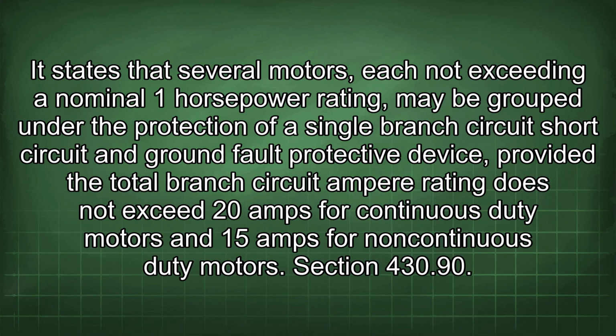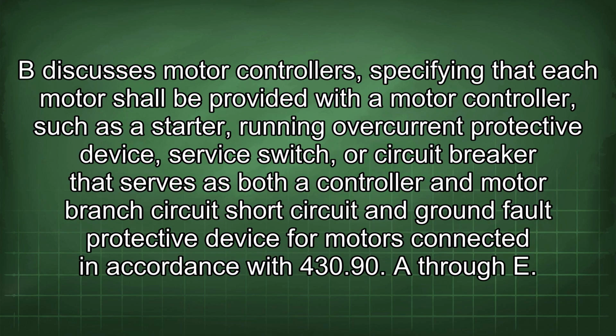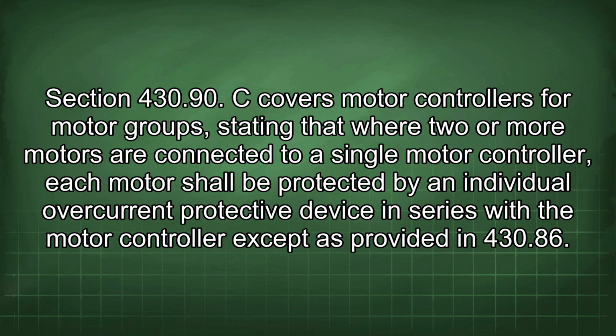Section 430.90 B discusses motor controllers, specifying that each motor shall be provided with a motor controller such as a starter, running overcurrent protective device, service switch, or circuit breaker that serves as both a controller and motor branch circuit short circuit and ground fault protective device for motors connected in accordance with 430.90 A through E.